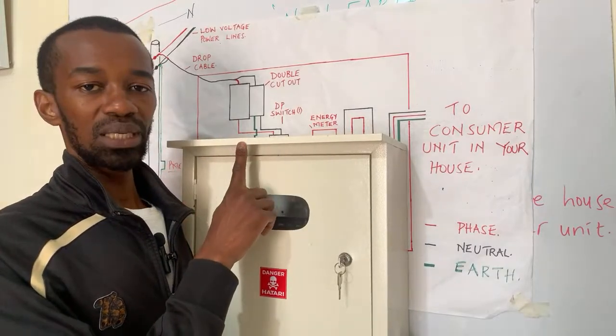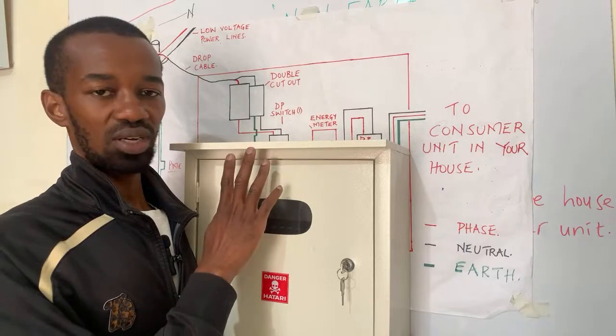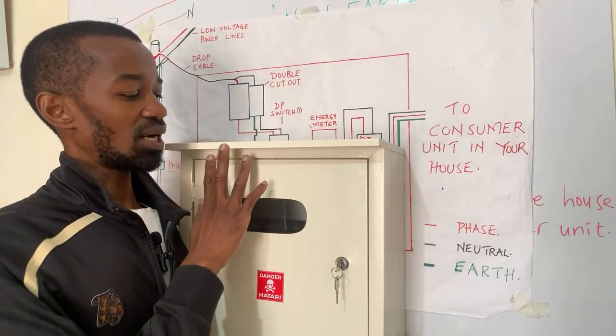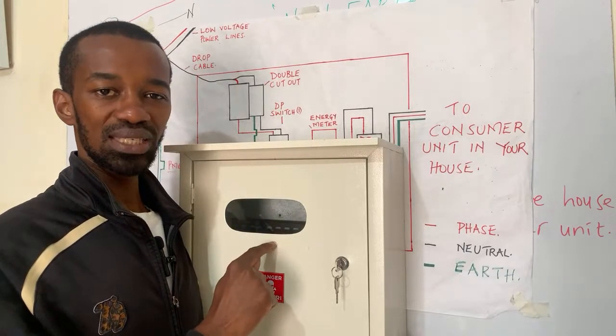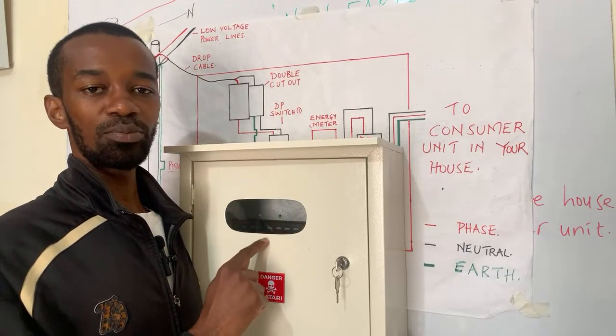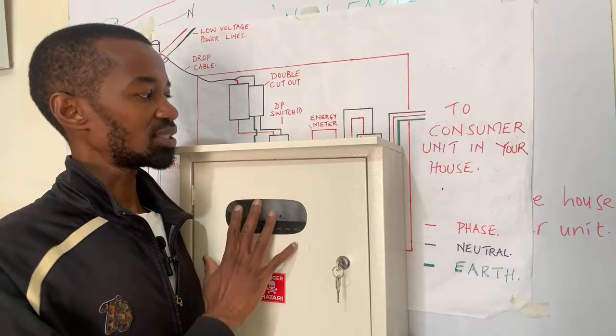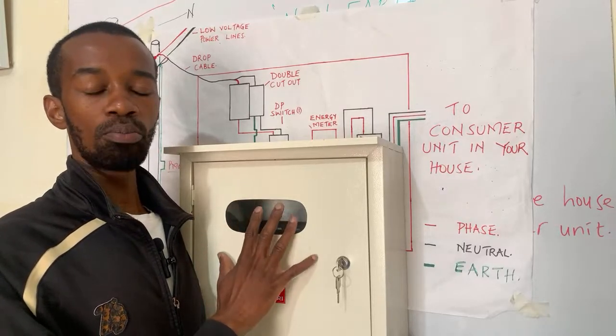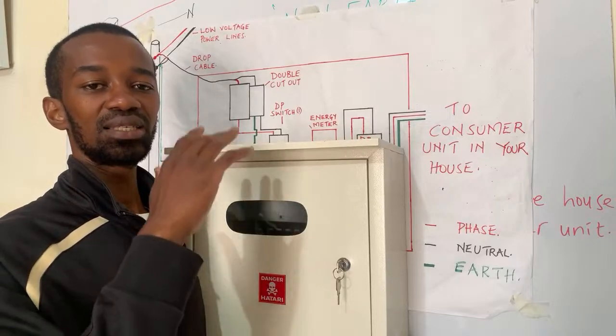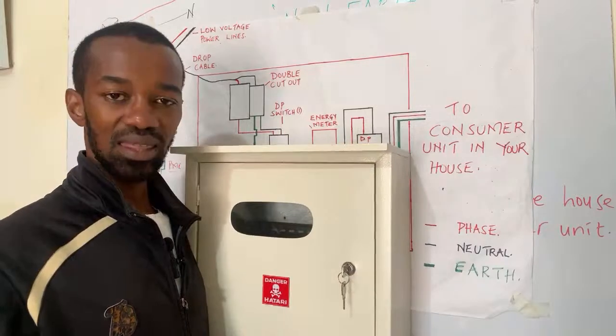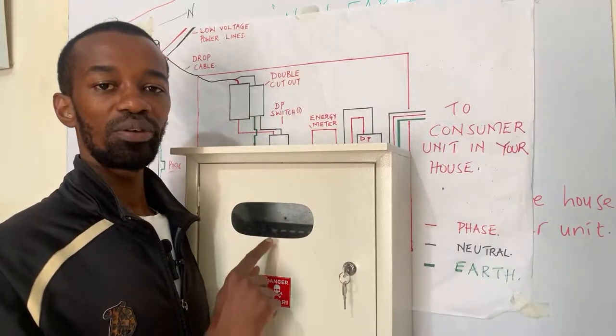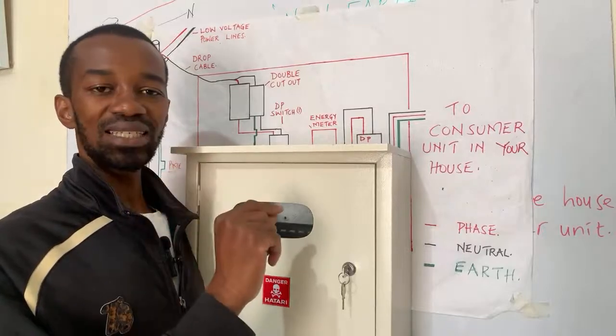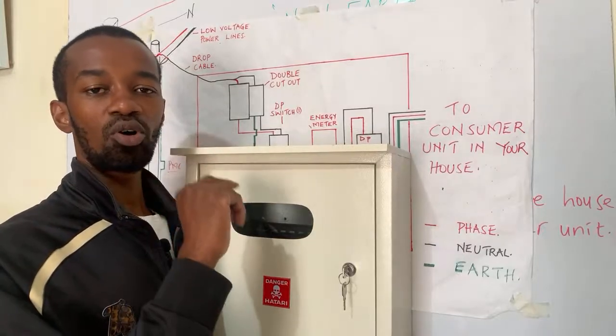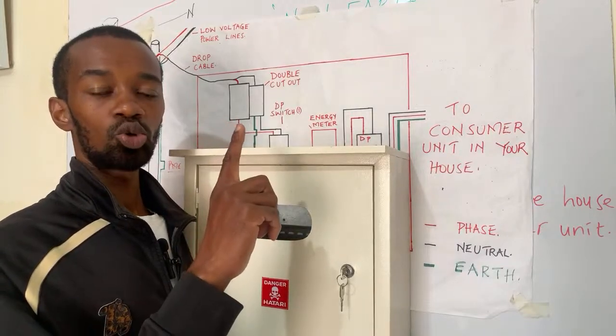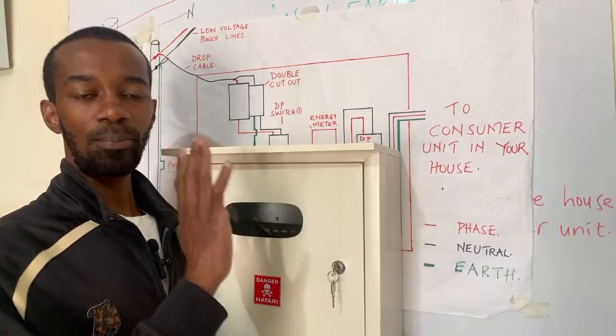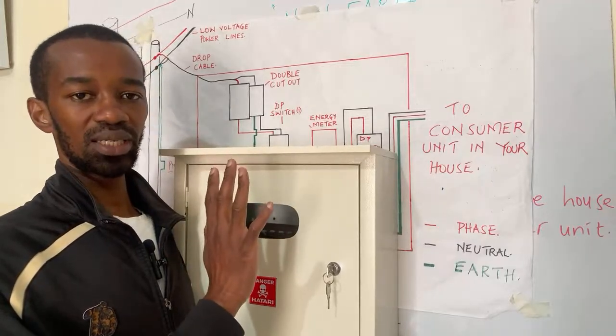So we will have this meter box welded onto that structure. The best thing an electrician can do is ensure the earthing on this meter box is perfect. When you go to that metallic structure or setup, whether it's a home or a business, and it is made of metals, the earth connection to the meter box should be very perfect. Also, on that metallic structure, there should be several earthing points, not only one, to ensure it serves that structure properly. I will elaborate much more about that.